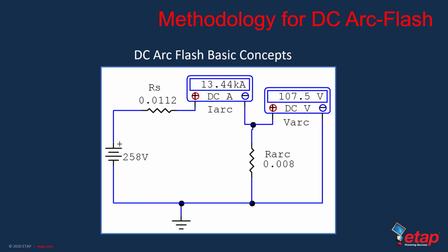So here is the concept that was presented in 2015. The high-level equivalent system representation shown in this slide of a DC power circuit tells us that for a shunt DC arc flash event, the amount of power delivered by the arc is proportional to the arc current and arc voltage. The arc voltage, of course, is dependent on the voltage drop across the anode and cathode, plus the voltage drop across the arc column. The length of the arc column can be empirically estimated as a function of the conductor material and the gap between conductors.